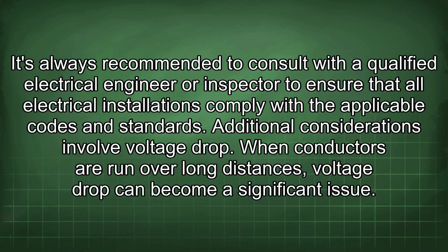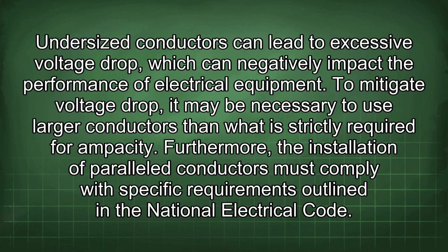Additional considerations involve voltage drop. When conductors are run over long distances, voltage drop can become a significant issue. Undersized conductors can lead to excessive voltage drop, which can negatively impact the performance of electrical equipment. To mitigate voltage drop, it may be necessary to use larger conductors than what is strictly required for ampacity.